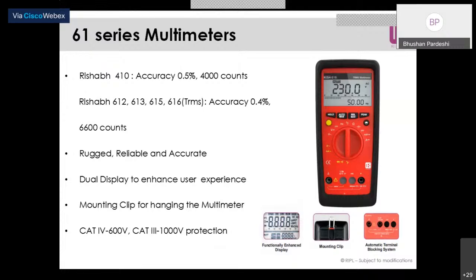Cat 2 mainly involves low voltage circuits during measurement. Cat 4 goes directly to transmission lines, like 11 kV lines or main incomer panels of an industry. Cat 3 is used for building wiring, building instrumentation, or distribution boxes in a building. For that case, category 3 multimeters are used.